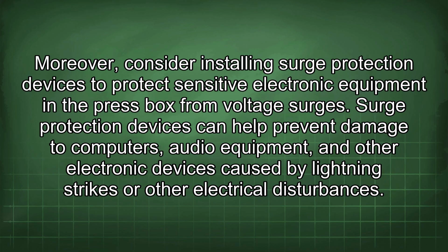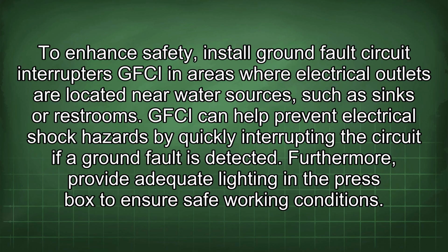Moreover, consider installing surge protection devices to protect sensitive electronic equipment in the press box from voltage surges. Surge protection devices can help prevent damage to computers, audio equipment, and other electronic devices caused by lightning strikes or other electrical disturbances. To enhance safety, install ground fault circuit interrupters (GFCI) in areas where electrical outlets are located near water sources, such as sinks or restrooms. GFCI can help prevent electrical shock hazards by quickly interrupting the circuit if a ground fault is detected.